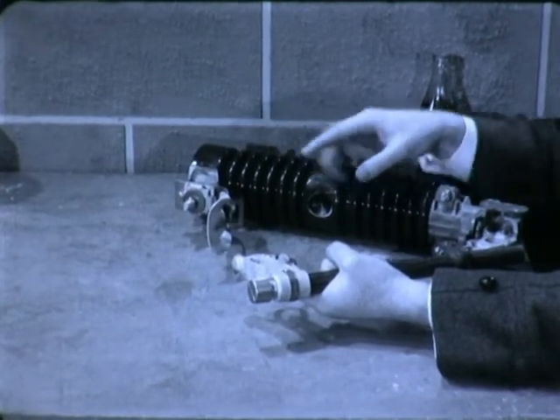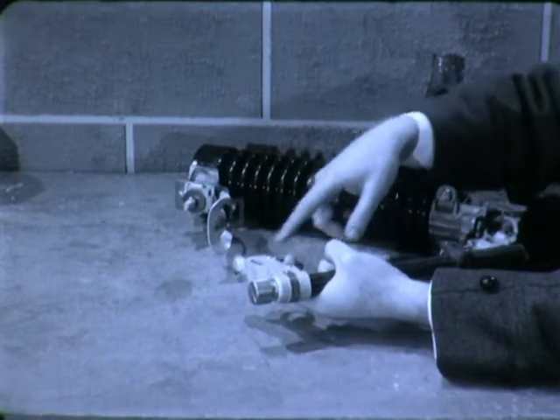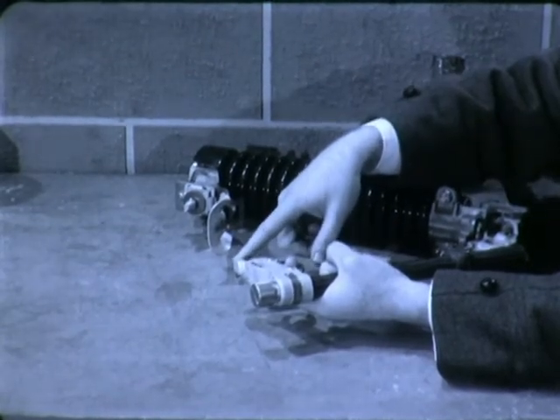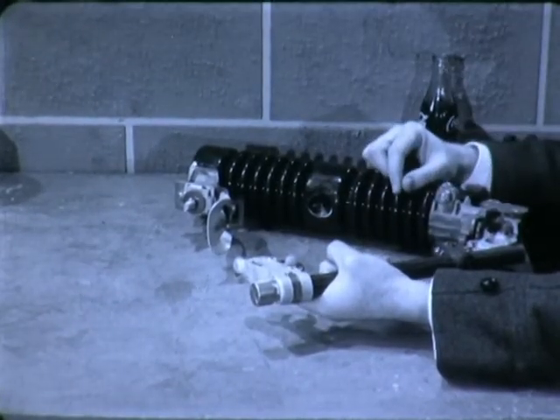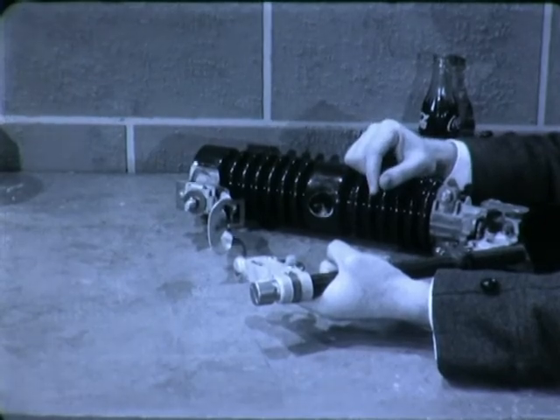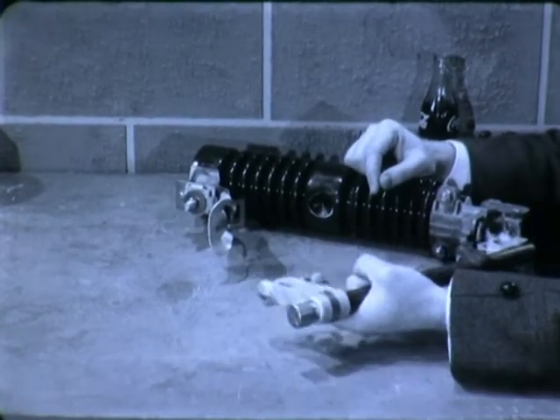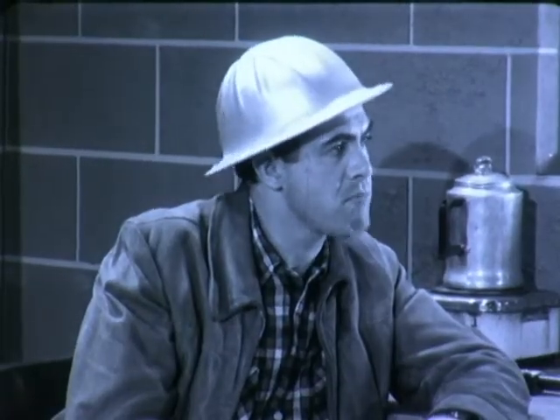All you do is pull this trigger. The end of the cartridge burns off, CO2 is released, and extinguishes the arc. Simple. Then you reload with a new cartridge, and you're cut in again.